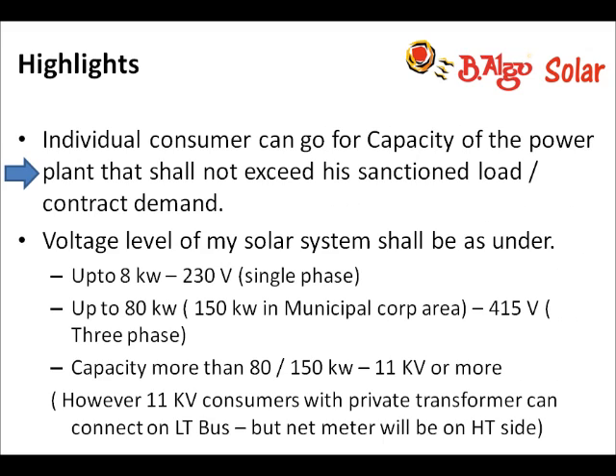The second limitation will be the capacity of the transmission line laid from your distribution transformer to your premises. Hence, the capacity of the power plant will be restricted to your sanctioned load. If you have a sanctioned load of less than 8 kilowatt, you can grid tie at 230 volts single phase. If you have a sanctioned load which is more than 8 kilowatt and is less than 150 kilowatts for municipal corporation areas or 80 kilowatt in other locations, you are permitted to have grid tie at LT 3 phase, that is 415 volts.